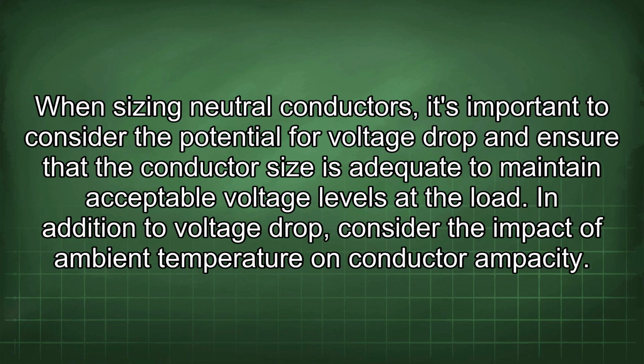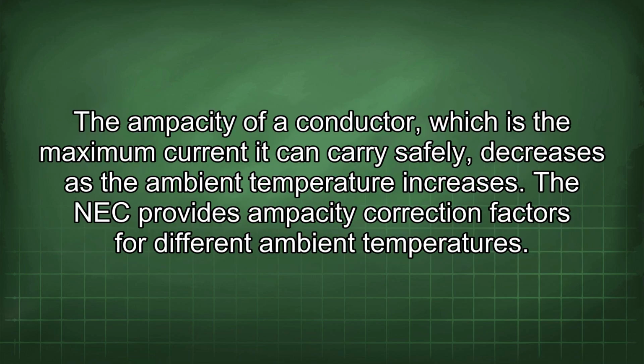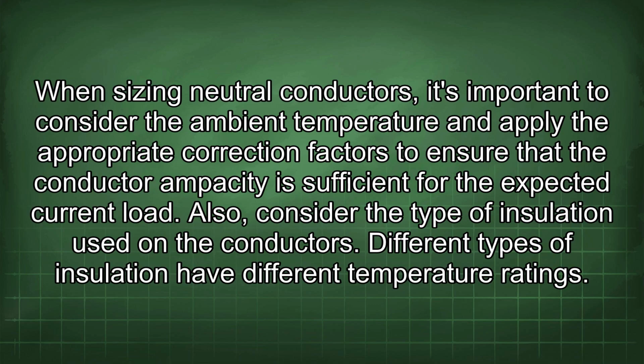In addition to voltage drop, consider the impact of ambient temperature on conductor ampacity. The ampacity of a conductor, which is the maximum current it can carry safely, decreases as the ambient temperature increases. The NEC provides ampacity correction factors for different ambient temperatures. When sizing neutral conductors, it's important to consider the ambient temperature and apply the appropriate correction factors to ensure that the conductor ampacity is sufficient for the expected current load.